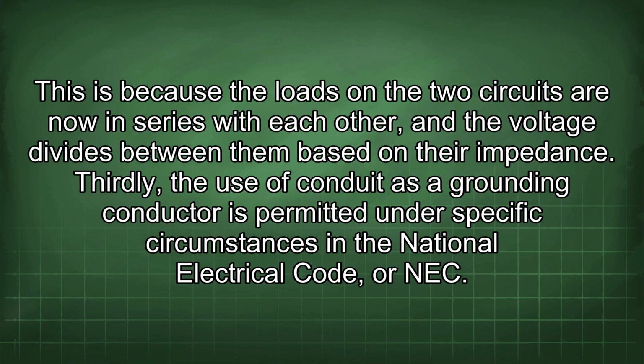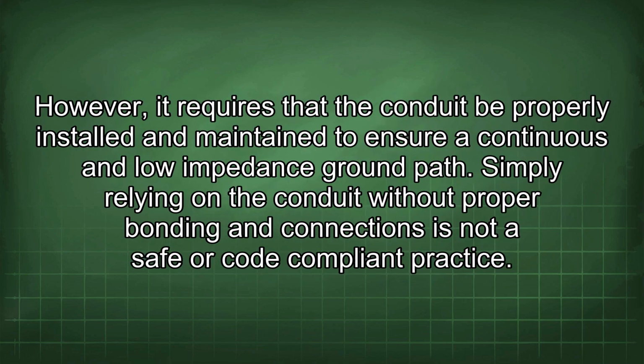Thirdly, the use of conduit as a grounding conductor is permitted under specific circumstances in the National Electrical Code, or NEC. However, it requires that the conduit be properly installed and maintained to ensure a continuous and low impedance ground path. Simply relying on the conduit without proper bonding and connections is not a safe or code-compliant practice.